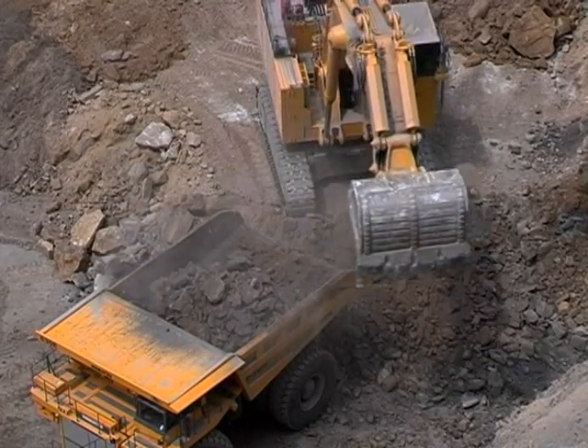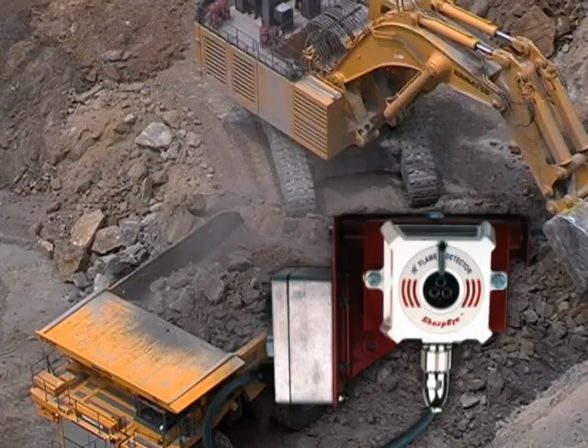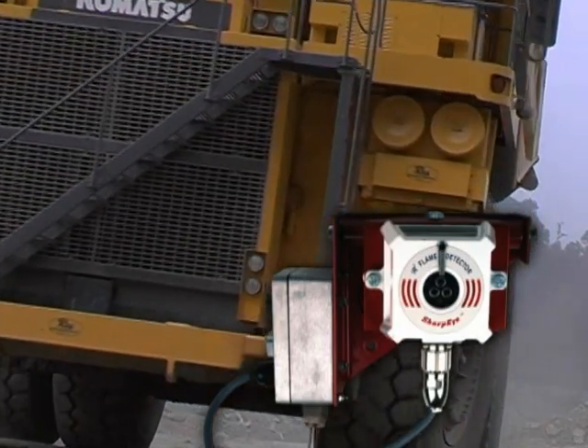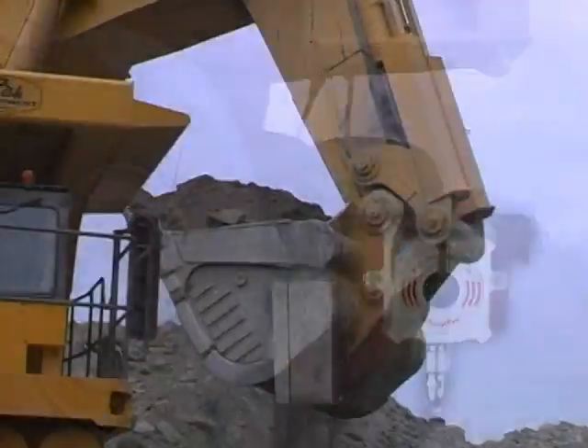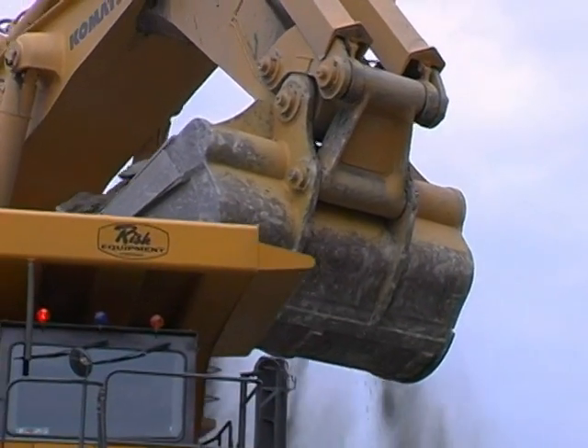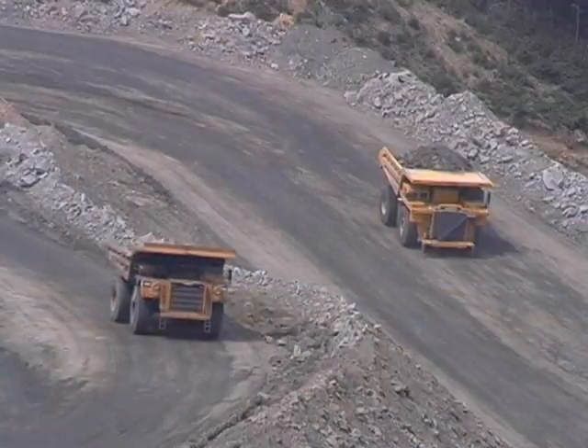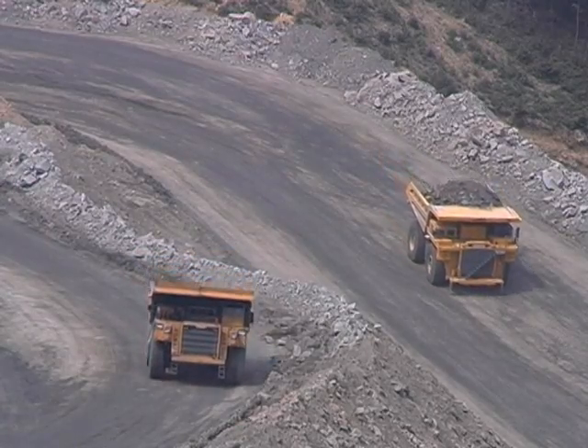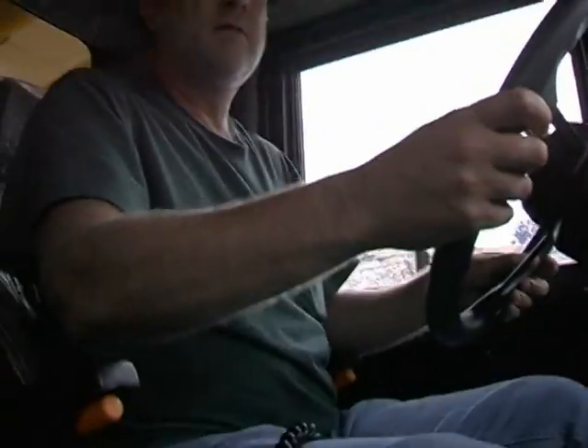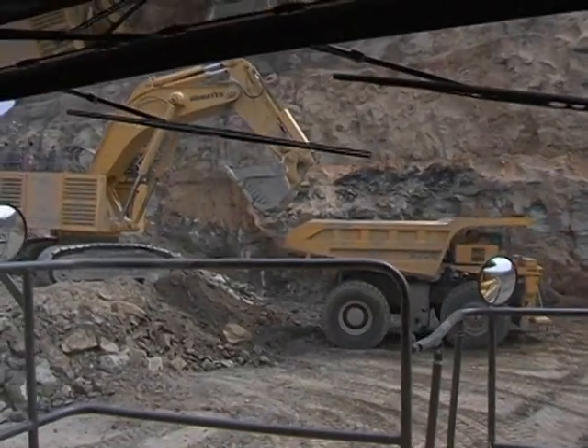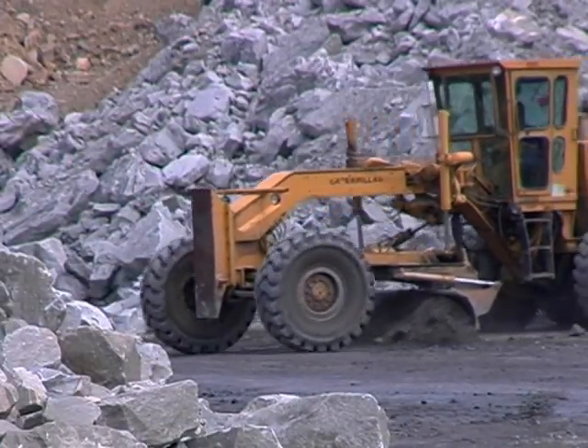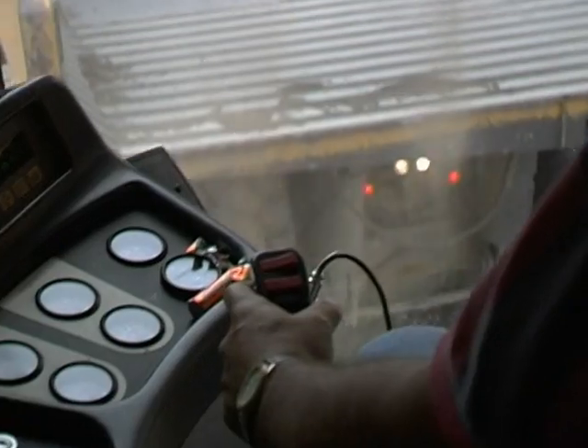For optimal protection, add the FM-approved triple IR flame detector to the Check Fire detection and control actuation system. This system has been designed specifically for use in the mining industry to provide additional fire detection in extreme conditions. ANSUL triple IR detection reacts in seconds, triggering the Check Fire module and signaling to the operator to evacuate the machine. Given the cost of today's new machinery, this improved detection speed can further limit fire damage. The triple IR flame detector is a heavy-duty detection system with added immunity to false alarms.